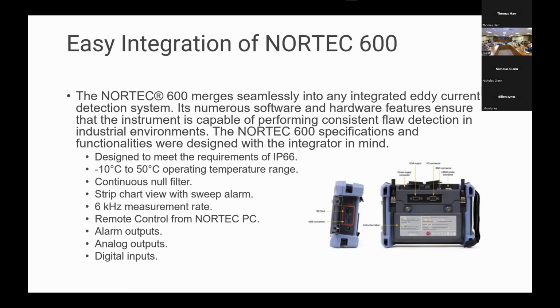So, easy integration of the Nortec 600. It merges seamlessly into any integrated eddy current detection system. Its numerous software and hardware features ensure that the instrument is capable of performing consistent flaw detection in industrial environments. The Nortec 600 specifications and functionalities were designed with the integrator in mind. So operating temperature minus 10C to 50C, continuous null filter, strip chart view with the sweep alarm, 6 kilohertz measurement rate, remote control from Nortec PC as well. So all these things make it easy to integrate this into a system for automated inspection.